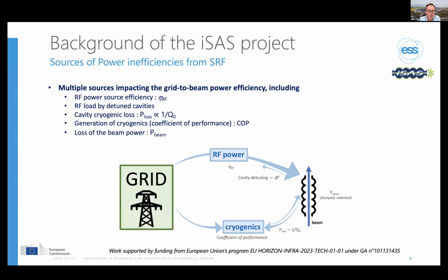So to improve sustainability, we must analyze the entire energy chain. In superconducting RF, there are multiple sources impacting the grid to beam power efficiency. This includes the efficiency of the RF sources themselves, the RF load and the detuning of the cavities, and the cavity losses that then have an impact on the cryogenic system, how you refrigerate those cavities, and for example the coefficient of performance, which is a measure of efficiency of the cryogenic plants, and also the loss of the beam power when you actually need to dump the beam.